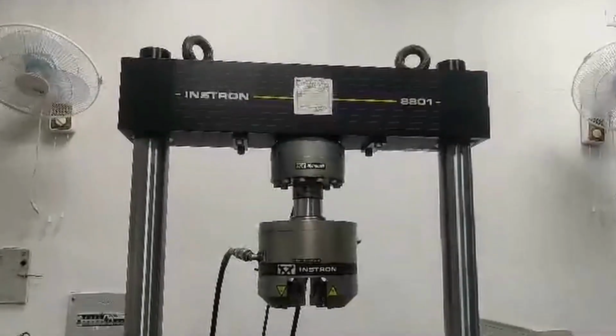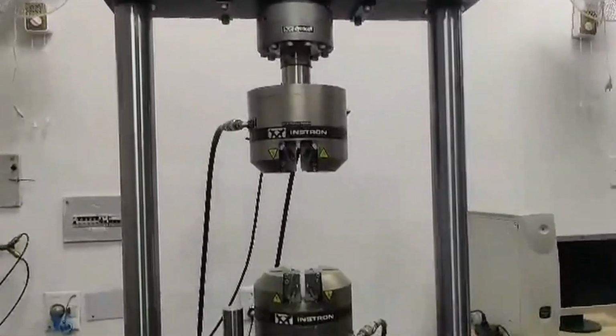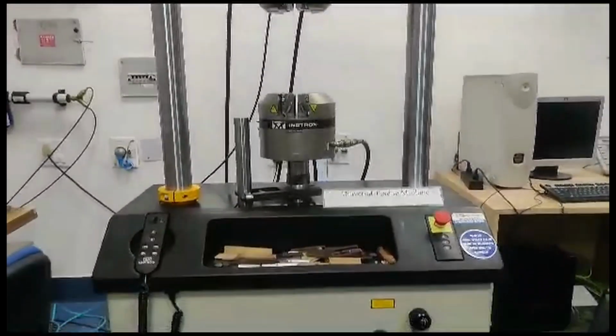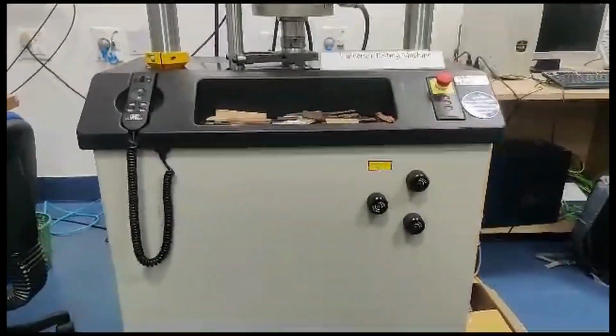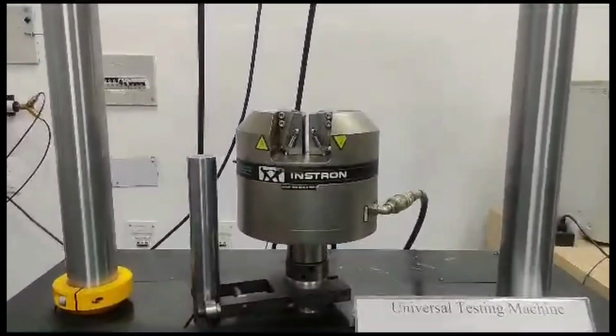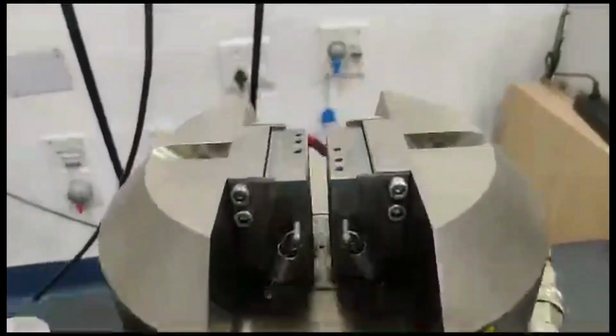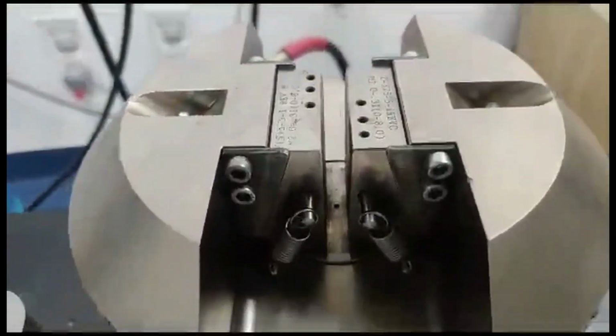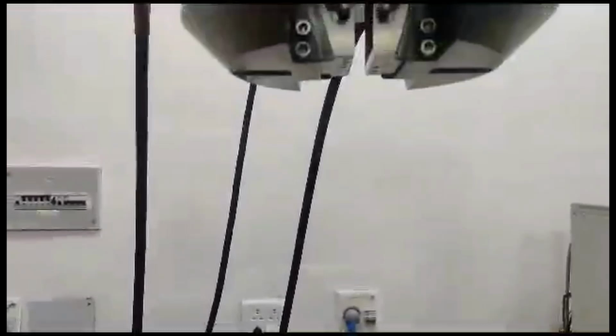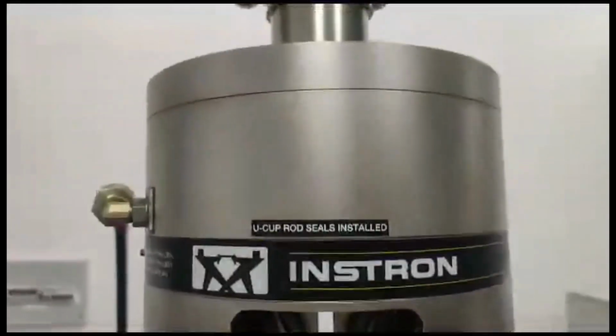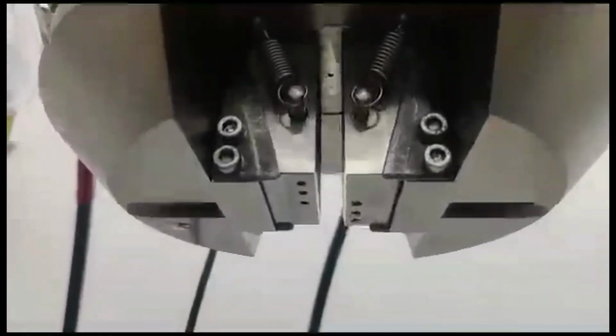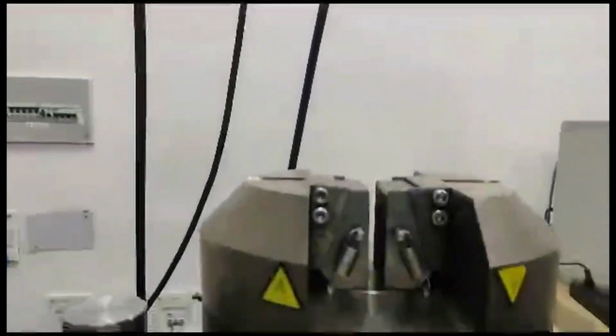The instrument here is the Universal Testing Machine, also called UTM, and the model that we have is Instron 8801. Its applications include tensile testing, compression testing, bend testing, and flexural testing. It comprises an upper jaw face and lower jaw face wherein the sample is placed in the middle, and with the help of the load cell the required force is applied.